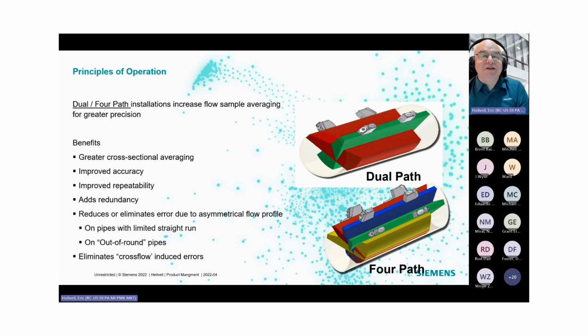Okay, so somebody just asked the question: the flow meter upstream pipeline configuration is changing based on valve operation, and we can see an effect currently in dual paths. Can we upgrade to 4? Okay, so if you currently have a dual path system, you'd actually have to change the transmitter in order and buy an additional 2 sets of sensors and mounts.